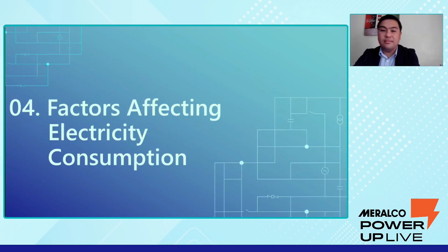Let me highlight a few factors affecting our cooling energy consumption. First is the room and building area. It is important to know the appropriate sizing of our cooling equipment to ensure we get the value for our money and attain the desired comfort level. Any capacity-area mismatch results in a 35 to 110% change in energy consumption, for both oversized and undersized scenarios.